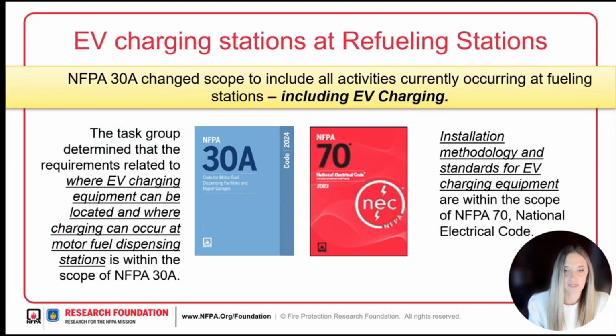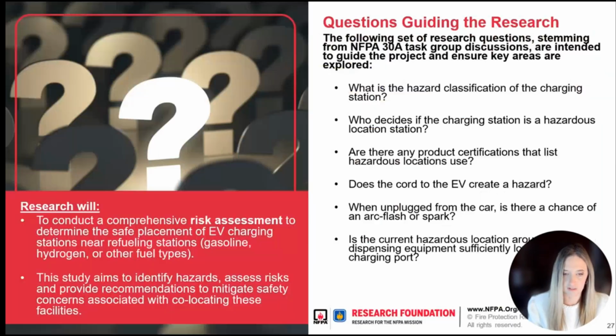There's been a lot of debate in NFPA codes and standards around where this guidance should live. The outcome was that where charging equipment can be located and where charging can occur at motor dispensing facilities falls within the scope of NFPA 30A, the code for motor fuel dispensing facilities and repair garages, while the installation methodology and standards for EV charging equipment are in our electrical code.